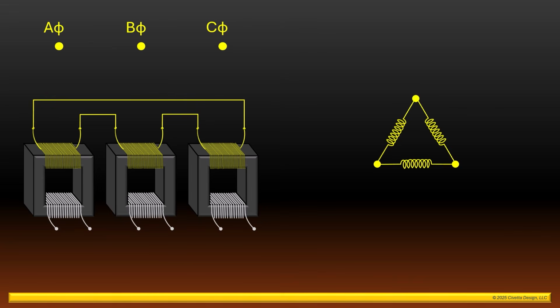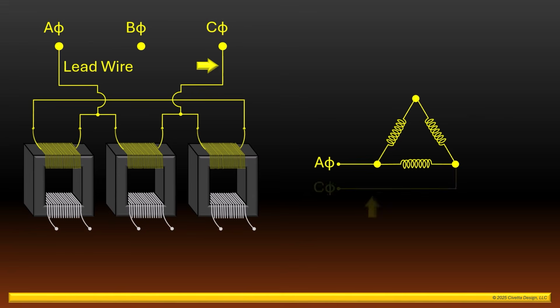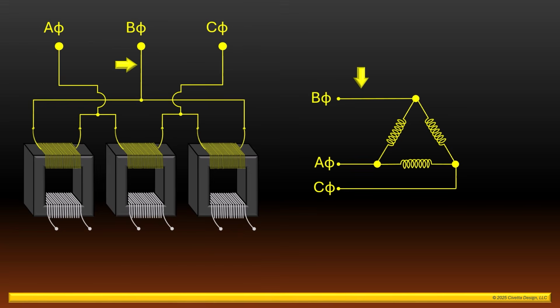We'll then connect the two transformers on the left with the A-phase primary conductor using a lead wire, also shown symbolically on the right. Similarly, we connect the two transformers on the right to the C-phase conductor with another lead wire. And finally, we can connect the two outer transformers to the B phase, which also completes the diagram on the right. This is called a primary delta connection. The primary windings of each of the three transformers are now energized at 12,000 volts using the three-phase conductors of the primary system. A neutral is not involved in this connection.